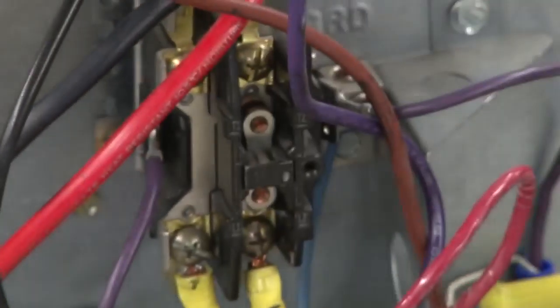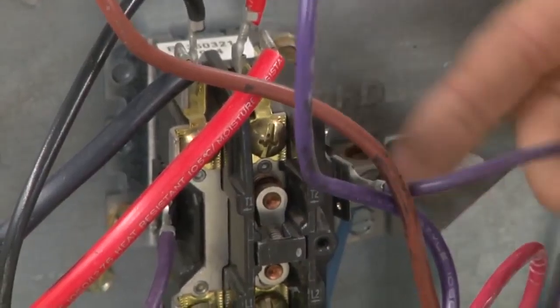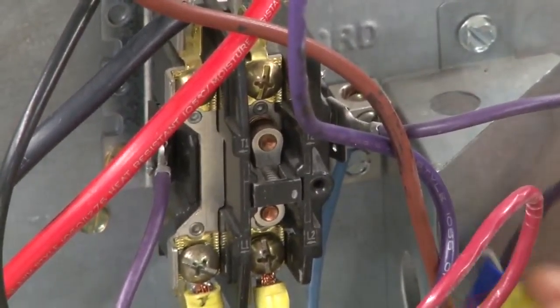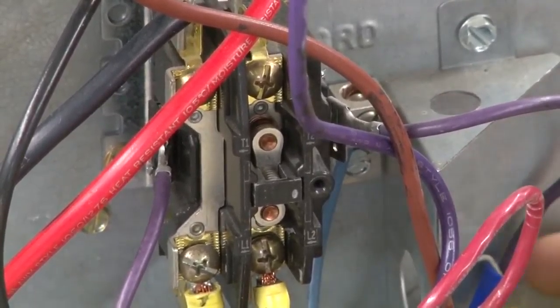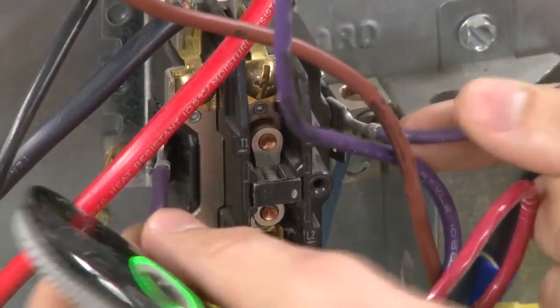This little device down here is your contactor. It's got a coil that is 24 volts that runs inside to your thermostat.